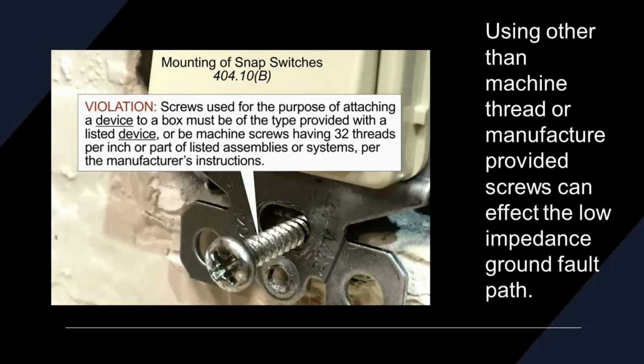So, right here, it must be a machine screw having 32 threads per inch or part of a listed assembly per the manufacturer's instructions. So, a 6-32, an 8-32, that's why the 10-24 doesn't work. It's got 24 threads instead of 32.